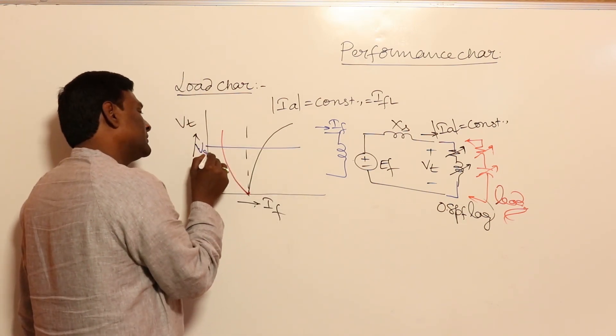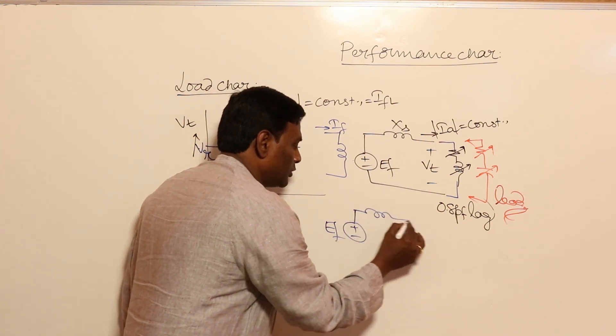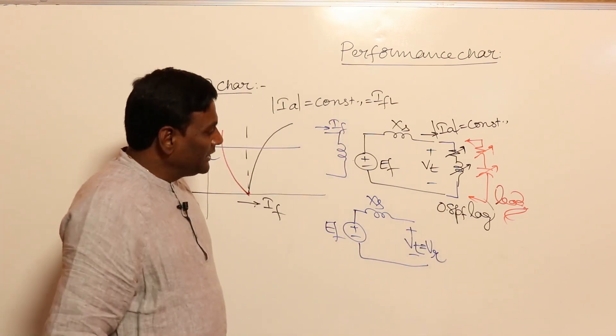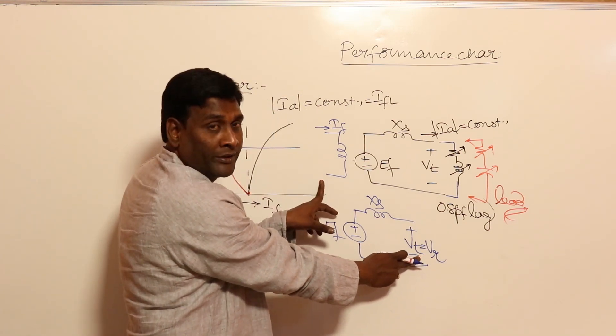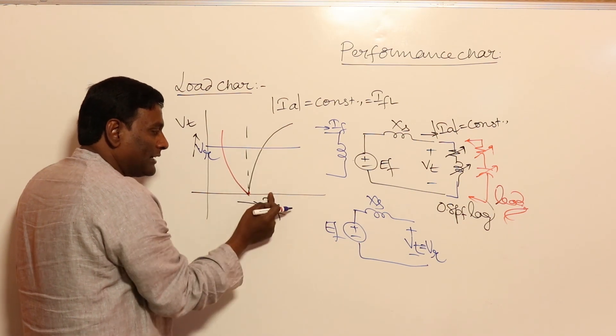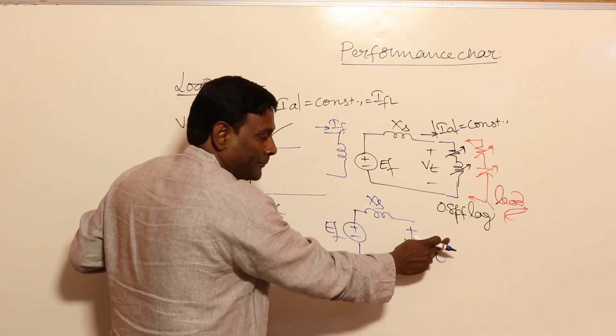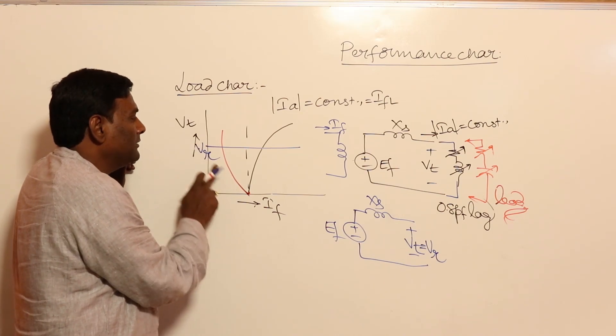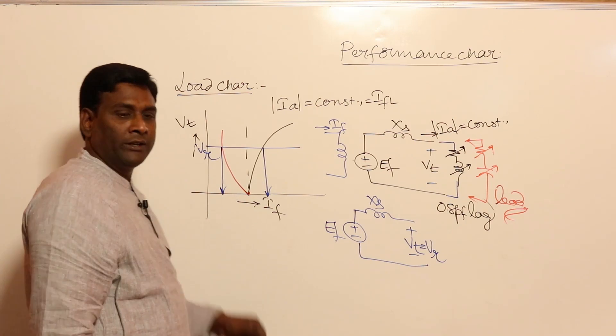How to remember this? Very simple — think of rated terminal voltage. If the load is lagging and terminal voltage is rated, EF must be more, so field current must be more. For rated voltage under lagging conditions, field current is higher. Under leading conditions, to maintain rated terminal voltage, EF should be less, so field current is less. Lagging: more field current; leading: less field current.